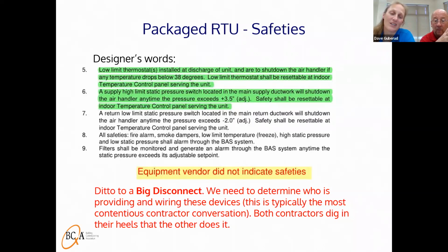Having said that, there are a lot of packaged rooftop units that do supply a low limit and a static pressure high limit off of the supply fan, and in those cases, they're resettable at the unit. However, in this case, they wanted them all resettable at the indoor temperature control panel. So really making sure that they're automatic resets, and then maybe having a latching relay down at your control panel is a way you can get by with that. So you still have that manual reset at your control panel in the building.